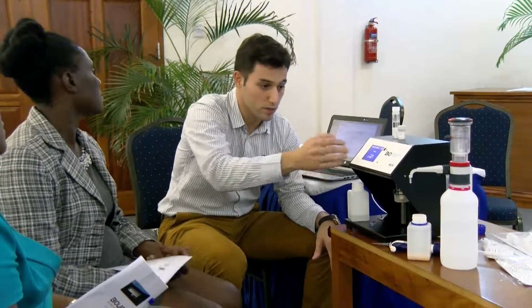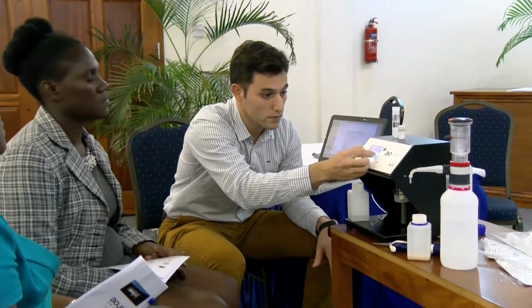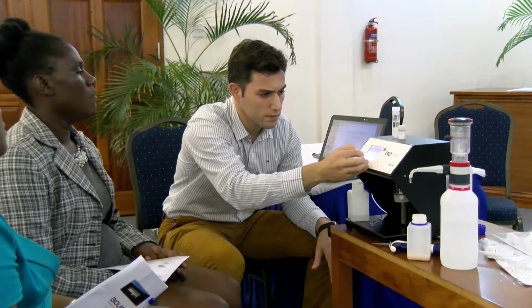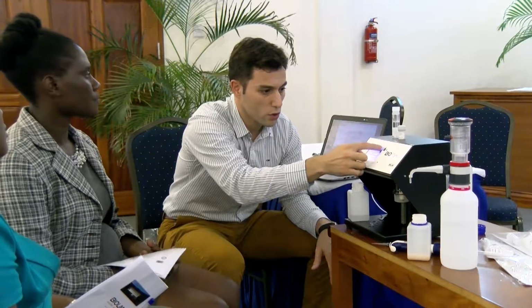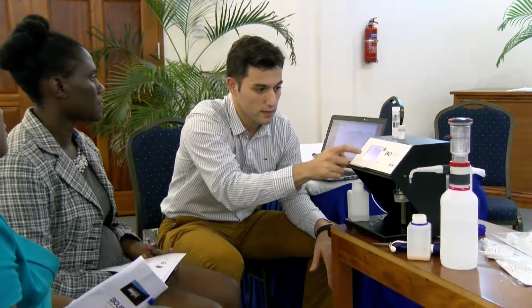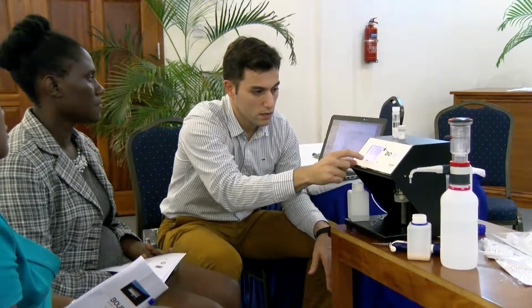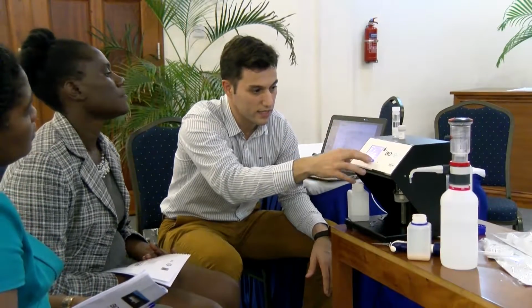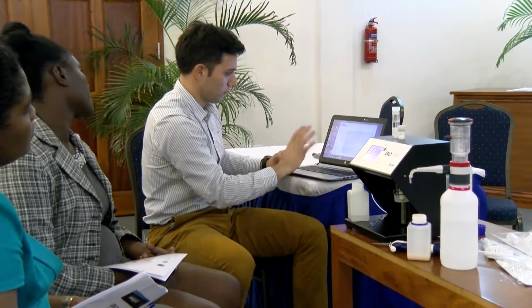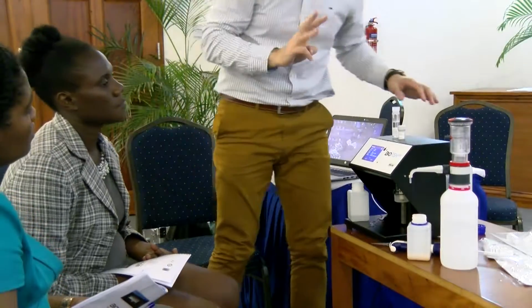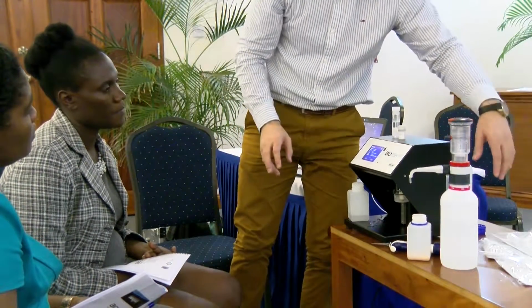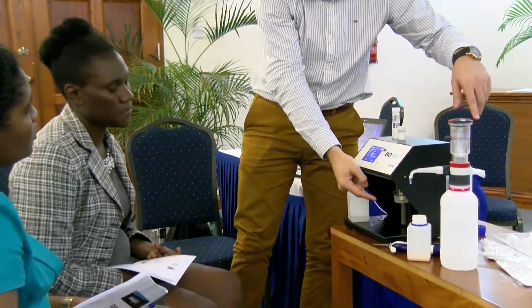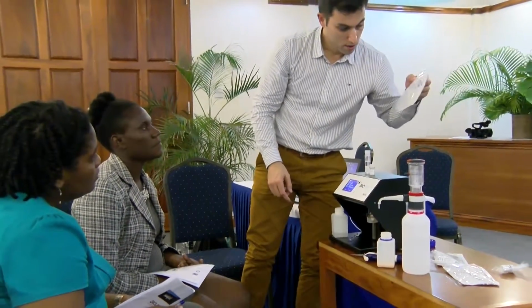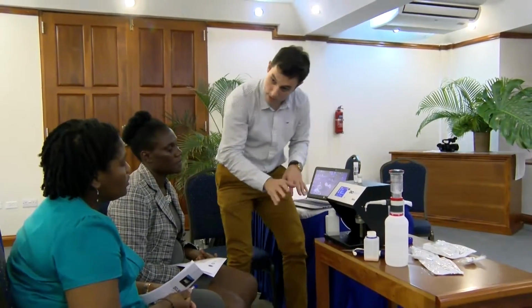If we make another analysis, we will have another sample. Sample 6. That's all. Now, if we go to records, histamine, you can see sample 4, sample 3. These are samples I made in the room before to try in the device. This is the basic functionality of the device. Take into account 3 reagents: measurement solution, which is used for everything and also to hydrate the biotest with the enzyme, the calibration reagent, and the biotest. That's all. The storage recommendations are in the manual.